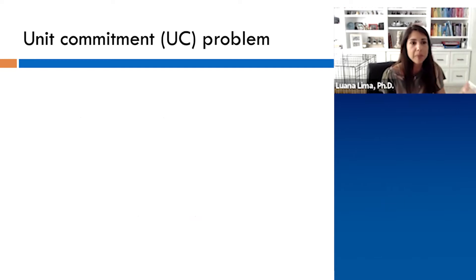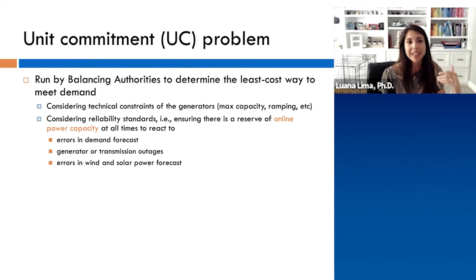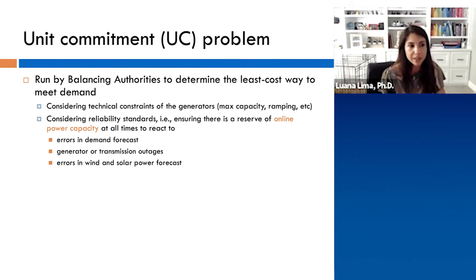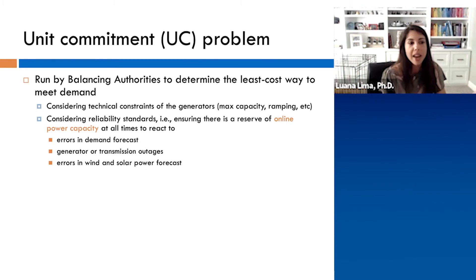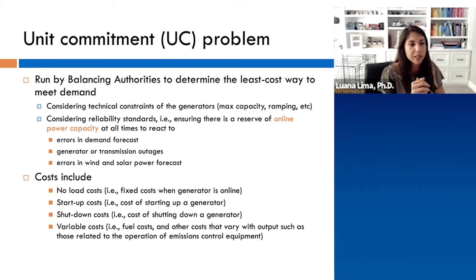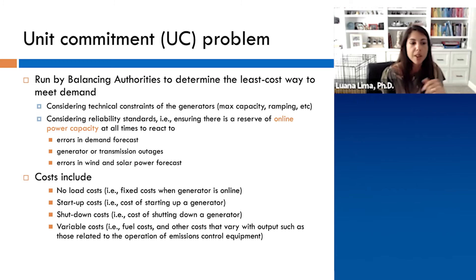The main optimization model run by vertically integrated utilities and ISOs is called unit commitment. It determines the least-cost way to meet demand. It accounts for the technical constraints of generators — like maximum capacity and ramping up and down — and reliability standards, meaning we need online capacity or reserves to account for errors in demand forecasts, generation and transmission outages, and errors in wind and solar power forecasts. Costs include no-load costs (the fixed costs to keep a generator online), startup and shutdown costs, and variable costs such as fuel costs for thermal plants.